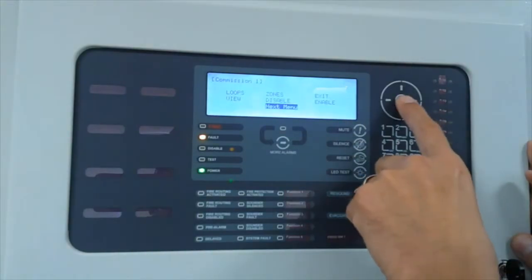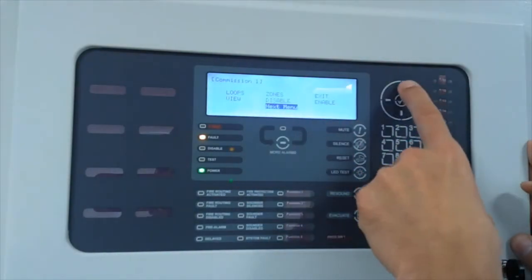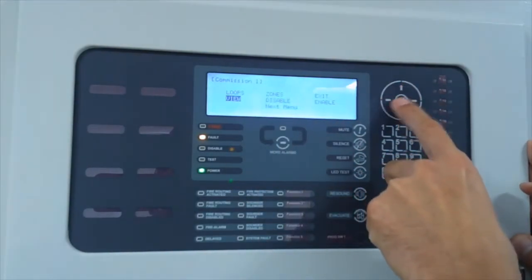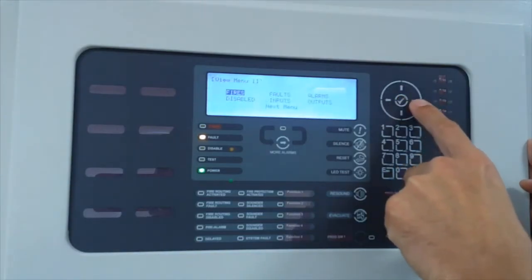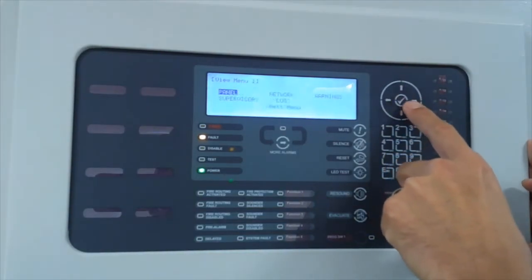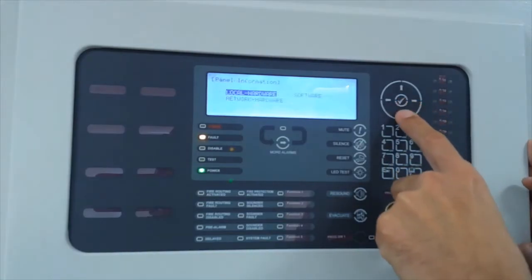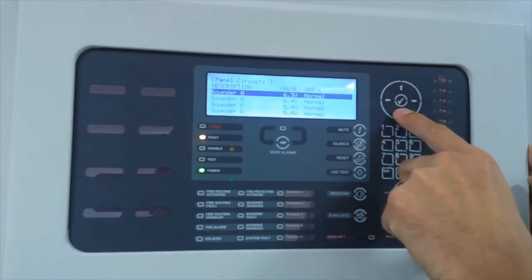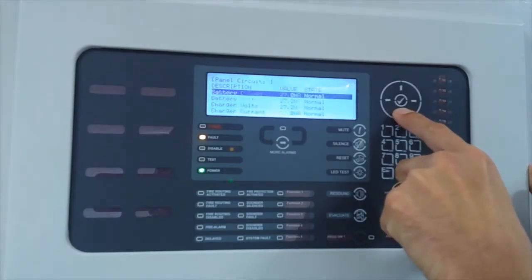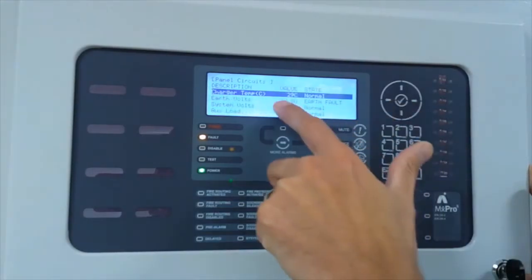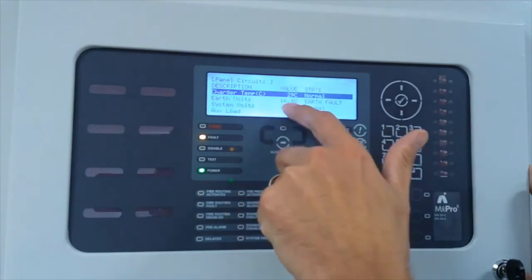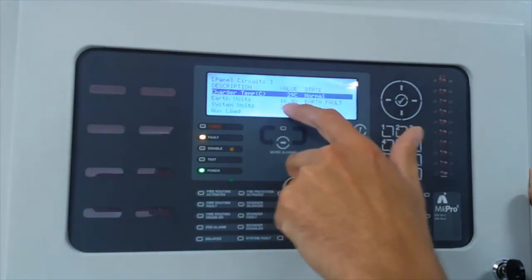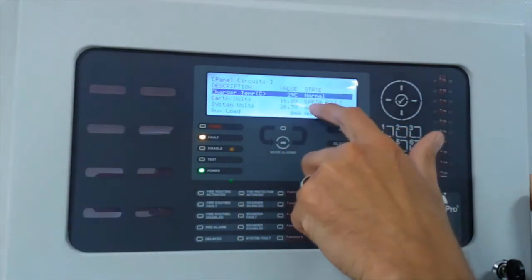Use the same menu structure, this view menu is in level 1 and level 2 and level 3. So if you go to view menu, next menu, panel, local hardware, I am going to scroll down to the earth fault. So we have got an earth fault on the system, we have identified it is high, greater than 2.5 volts, so it is a positive conductor at the ground.